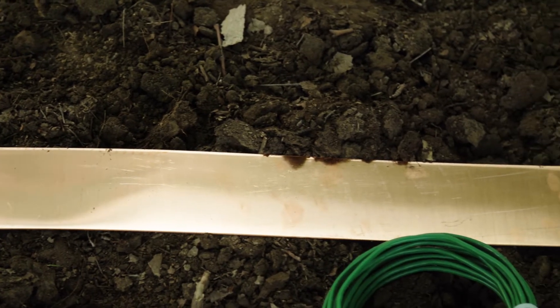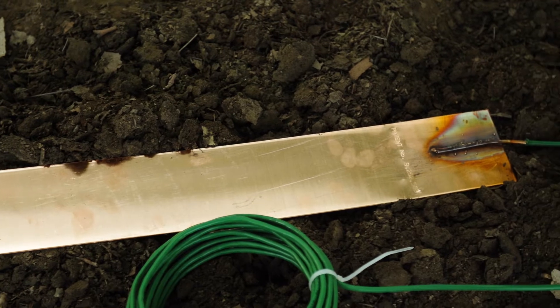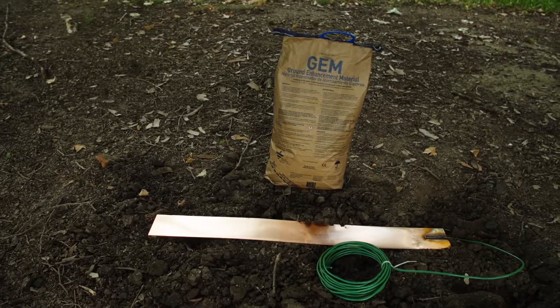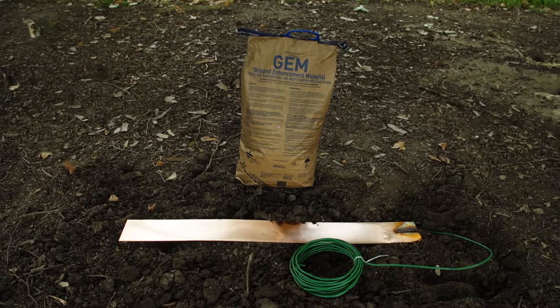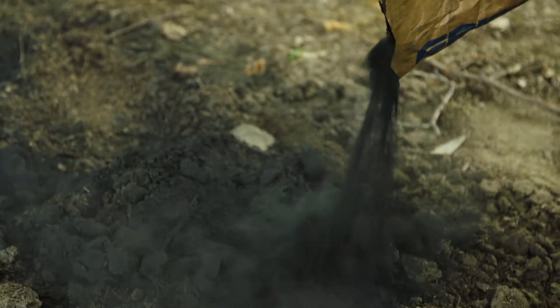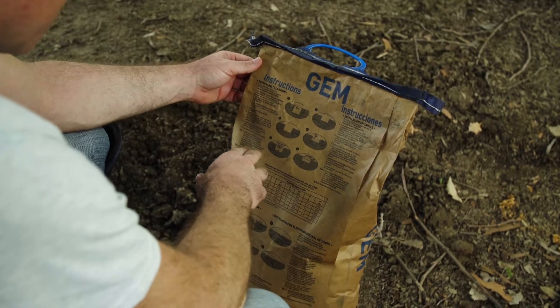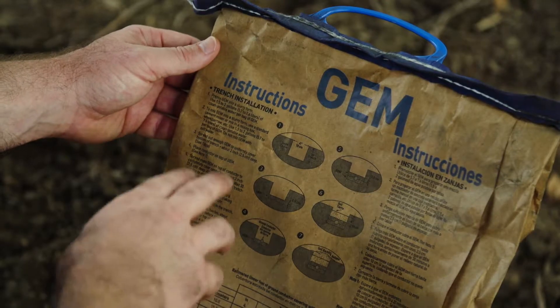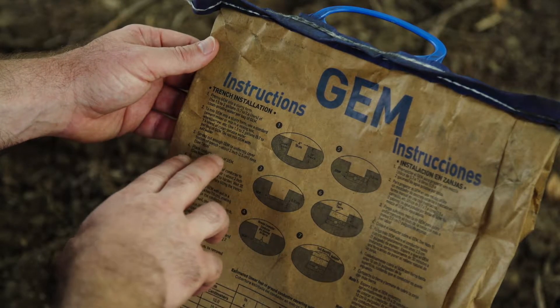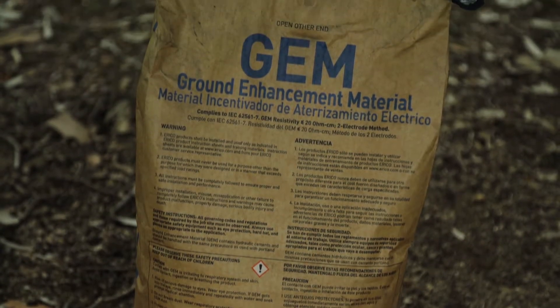Ground plates are easily installed in a mechanically dug trench and are supplied with an insulated copper conductor. Where necessary, the backfill soil around the ground plate can be enhanced with GEM ground enhancement material to achieve greater conductivity. Soils that are more porous or rocky often require this. When installed in the recommended amount based on soil conditions, GEM maintains constant resistance for the life of the system. It is supplied in 25-pound bags; contact the factory for calculation information.